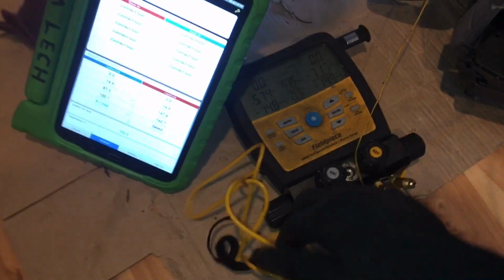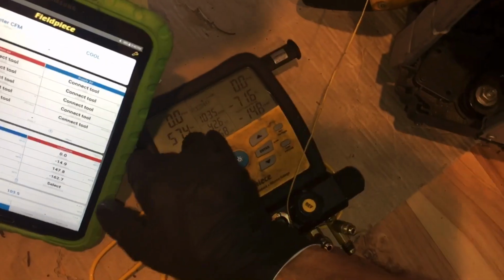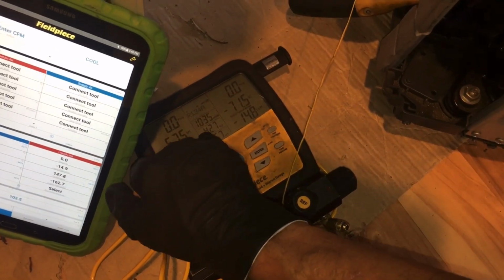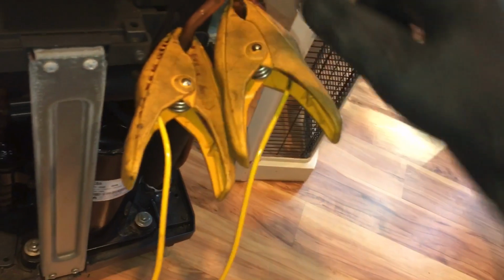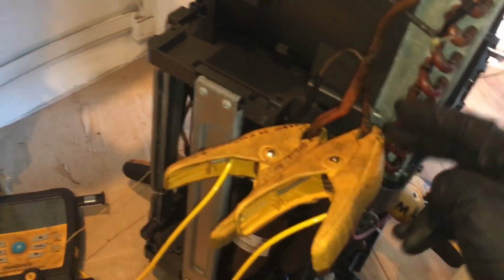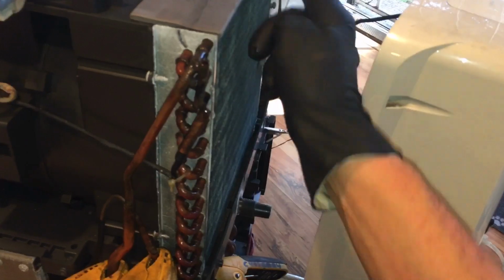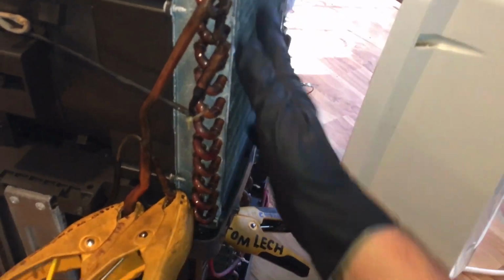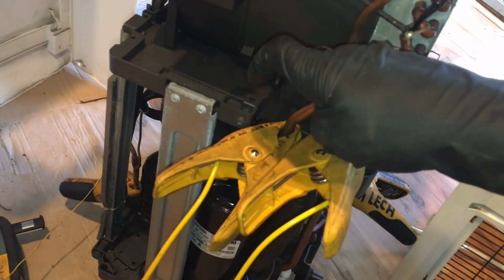So at this point right here, where it says suction line temperature, it's 42 degrees. So at this point where this capillary tube comes in, before it goes through the first part of the evaporator, 42 degrees. Then after going through back and forth, doing its job, cooling off the air in the room and condensing, making water, it comes back out. At this point, we lost some of the capacity.